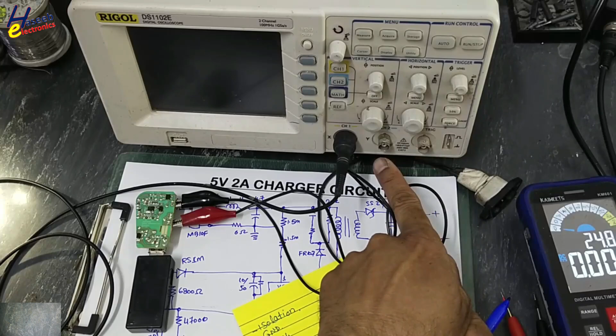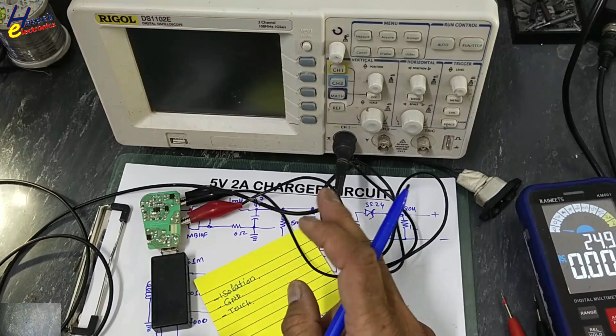We will not touch any metallic part of the oscilloscope, because when using an unisolated power supply line voltage with a 2-wire cable, even if we connect the oscilloscope's low side to ground, that is unisolated hot side ground, which may expose these metallic parts. So we will never touch these terminals. When we want to connect and probe any signal, we will take special care to remove power first, then connect the oscilloscope.